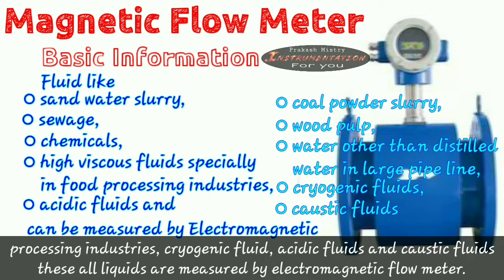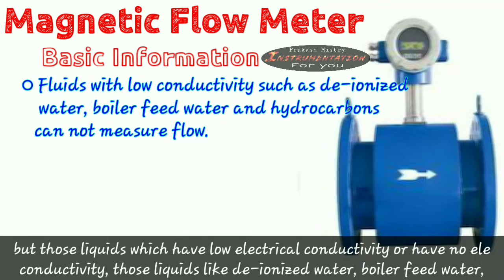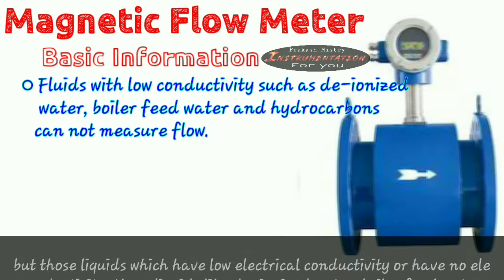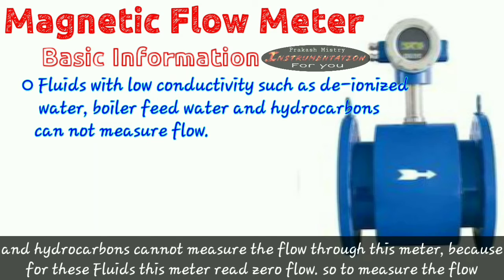These all liquids are measured by electromagnetic flow meter. But those liquids which have low electrical conductivity or have no electrical conductivity, like deionized water, boiler feed water, or hydrocarbons, cannot measure the flow through this meter.